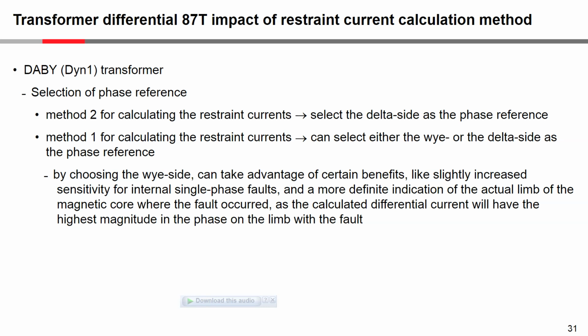So is there a better choice, Y or delta? Well, if you choose the Y side, there are certain benefits that maybe can be taken advantage of.